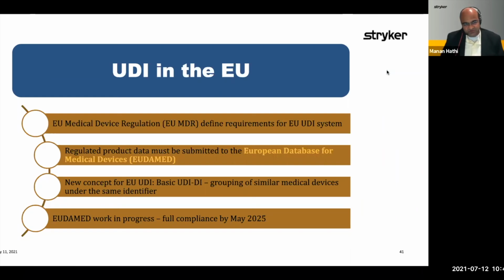They're also introducing a new concept called the Basic UDI-DI. It's more than just the UDI-DI, which I said is one single model or version of a device. Basic UDI-DI groups similar models into one if they have the same risk class and the same characteristics in terms of intended use. Then they give it one identifier. So they have a family level, and then they have the individual level.